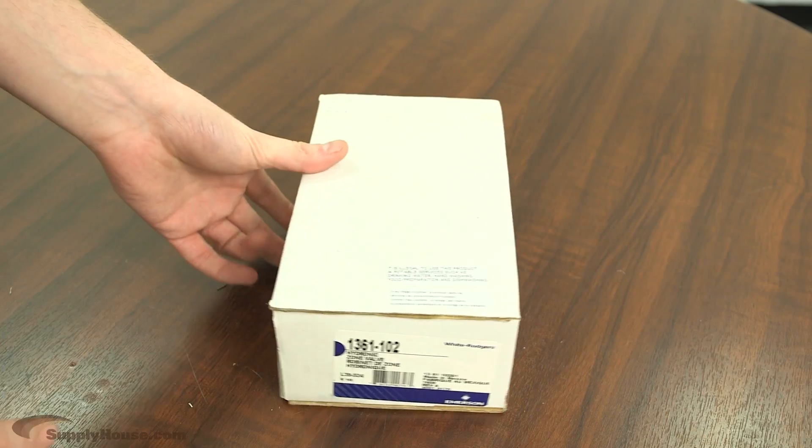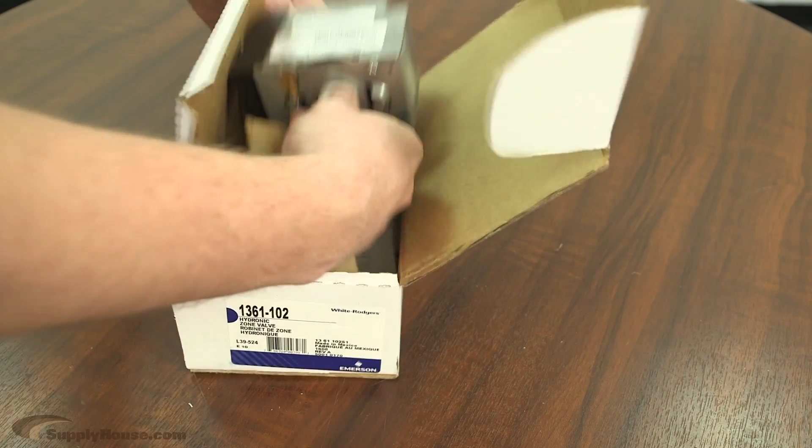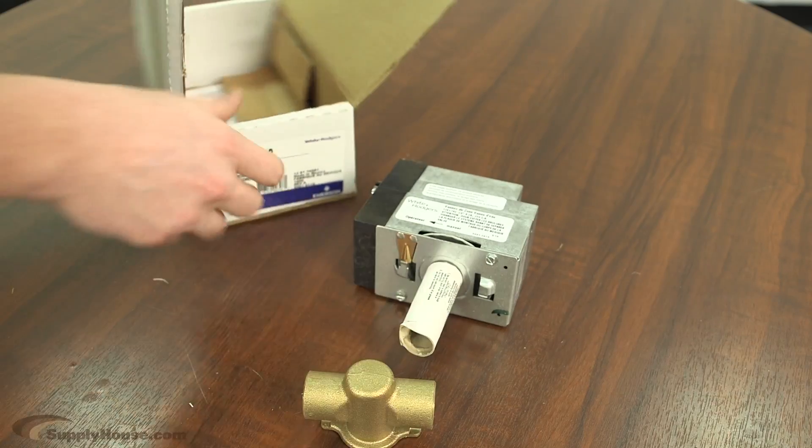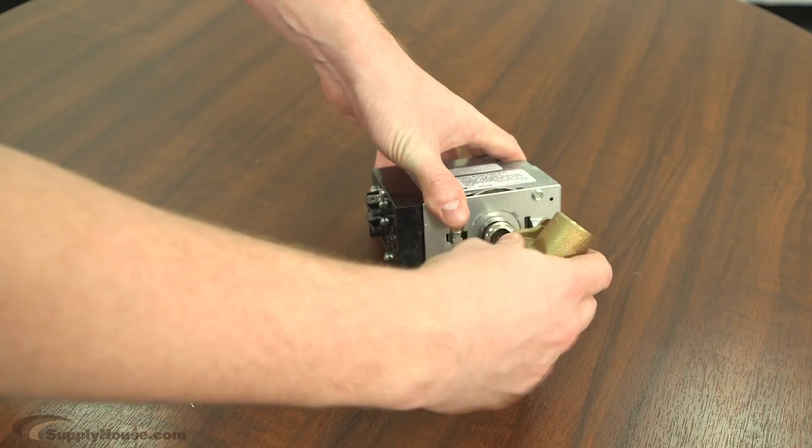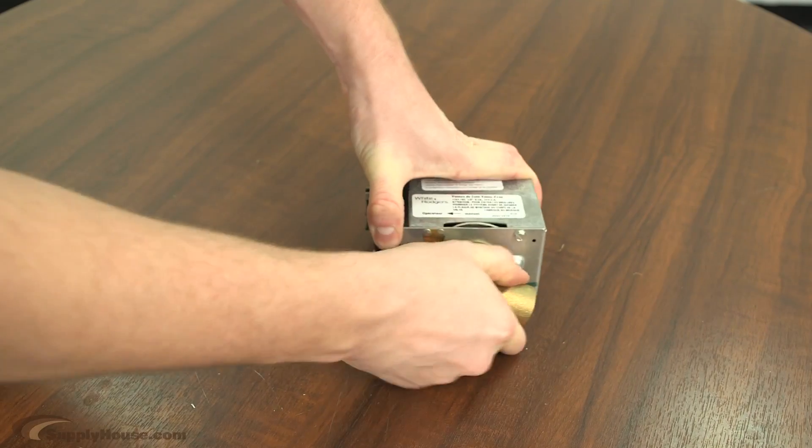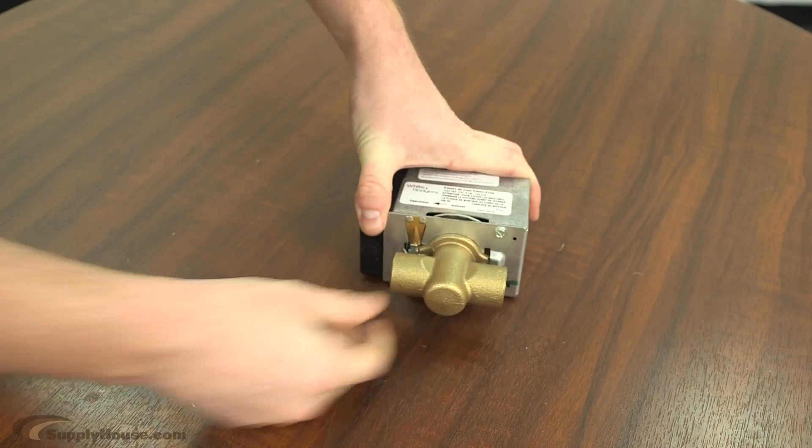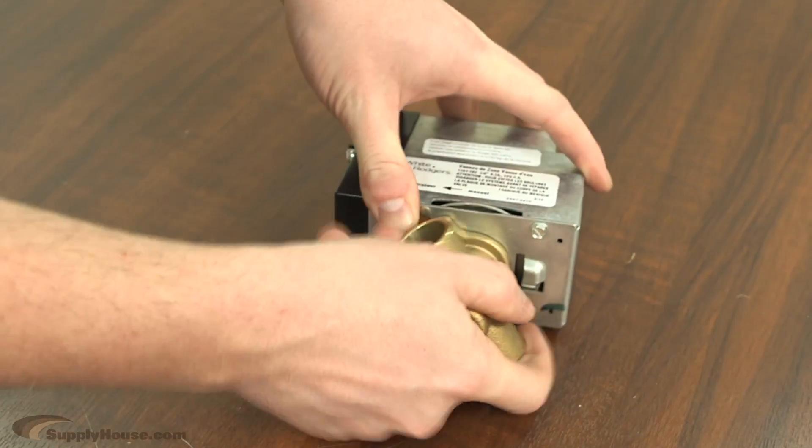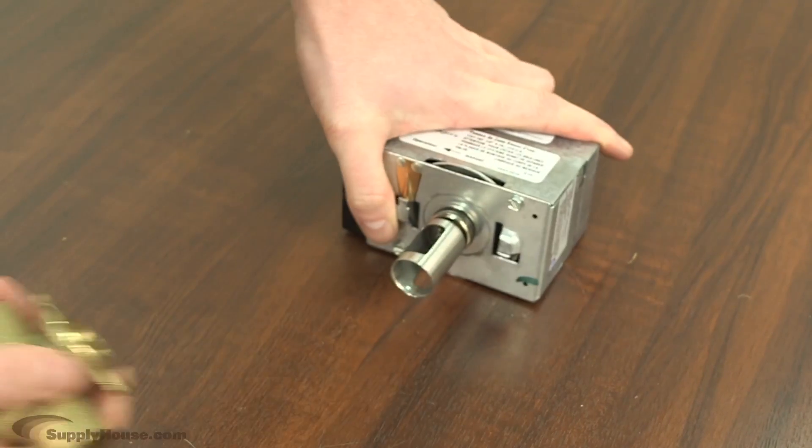Here we have the White Rodgers zone valves. They ship with the body and the actuator separate as well. So on these guys, you slide the body, and then push it down and twist it into these metal channels here. To release it, you press down this little tab, and the body twists and comes back out.